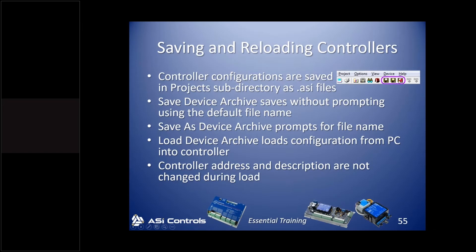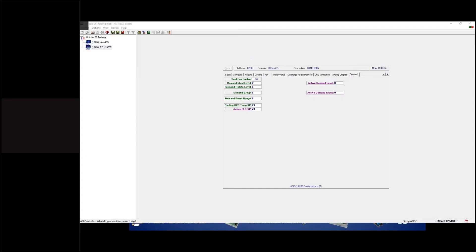Saving means taking a program from the controller and saving it onto your computer. The disk icon with the red arrow is to load a device archive, which means taking a program from the computer and putting it into the controller. When we load a configuration into a controller, some things don't change — including the controller's address, all the BACnet settings, and the description. Those don't get updated intentionally.